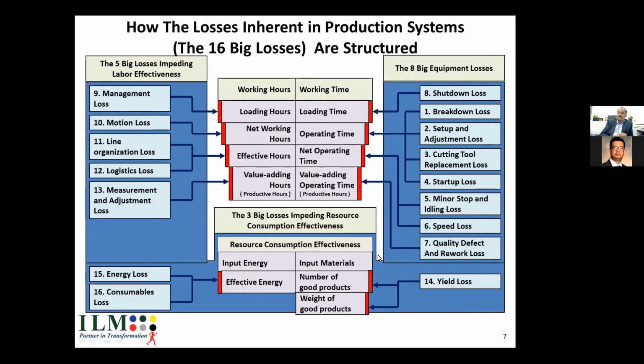Energy loss is steam, electricity, basically. Compressor air also. Compressor air basically means electricity loss again. So we need to take actions to control energy, steam leaks, okay, and boiler efficiency kind of exercises we have to do. Boiler efficiency means the proper cleaning of boiler tubes and all, using good water and checking the hardness and all, and then the steam leaks and insulations, pipelines, and using the correct steam traps and line sizing when you distribute the steam. Those things matter a lot when it comes to energy.